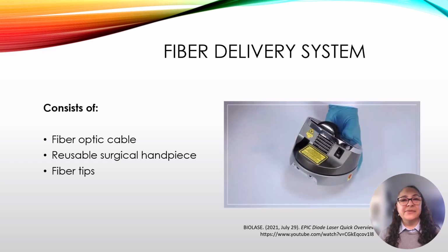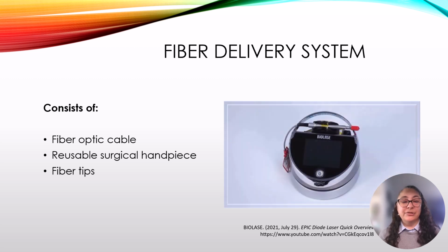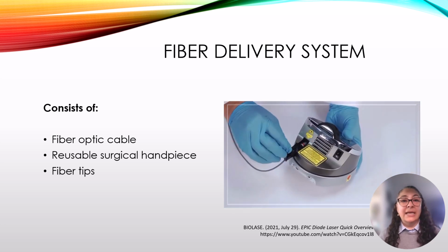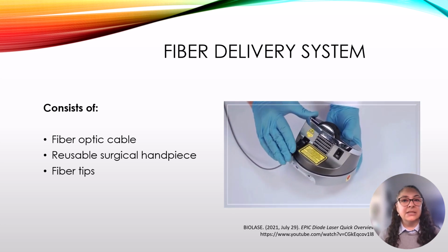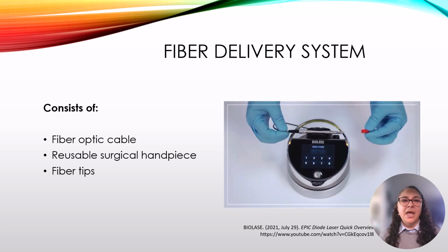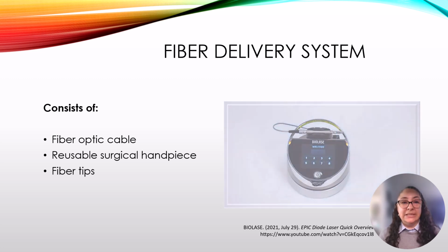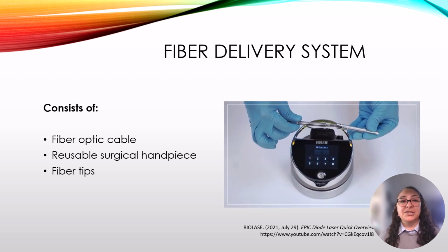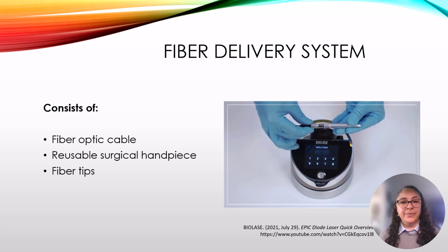The fiber delivery system consists of the fiber optic cable, a reusable surgical handpiece, and the fiber tips. As previously mentioned, the fiber optic cable transports laser energy from the base to the tip. Its glass tip is flexible but delicate, so handle it with care. The fiber optic cable can come pre-attached to the base console or detached as shown in this video. In this case, you will have to manually attach the fiber optic cable to the base console.